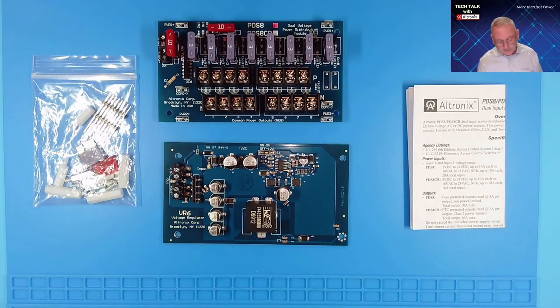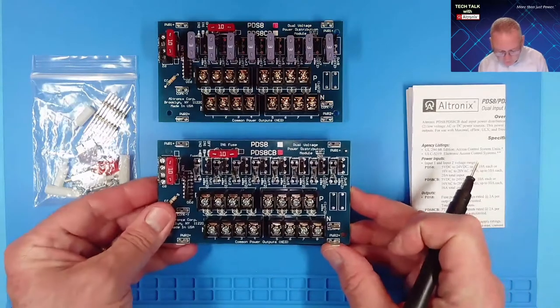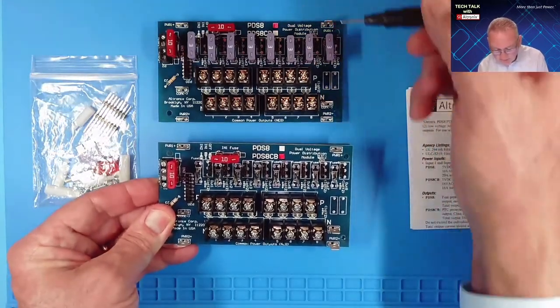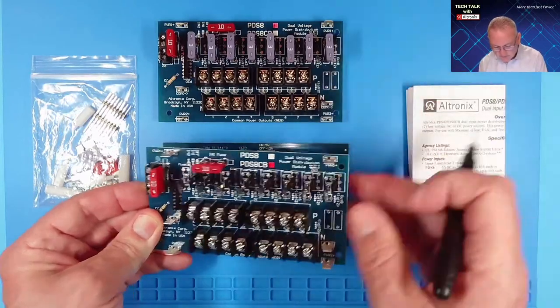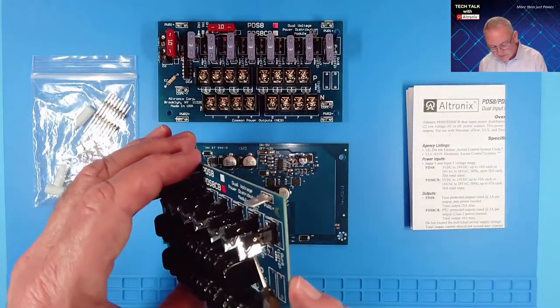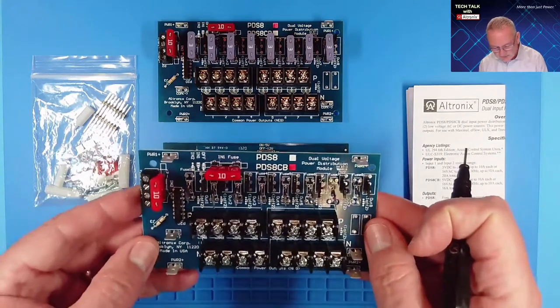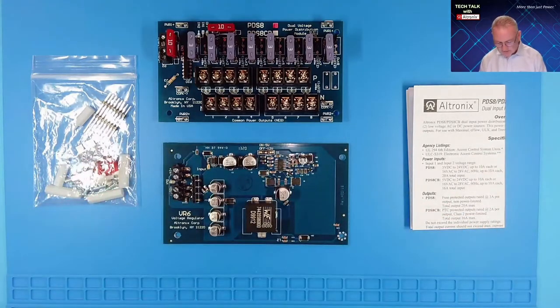Now this kit is also available in the PDS-8 CBK1. CB stands for circuit breaker. If we compare the two distribution boards, the PDS-8 has a 3-amp ATO fuse and the PDS-8 CB has a 2-amp PTC circuit breaker which is a power limited class 2 device. Other than that, the two boards are identical.